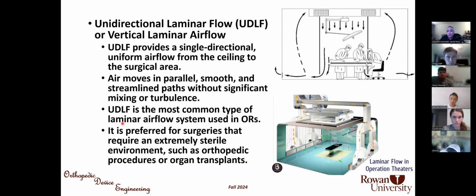Unidirectional or vertical one is the most efficient one and the most expensive one, and is usually used only for specific subspecialties like orthopedic surgery, neurosurgery, and organ transplant, where strict rules are important in sterility.